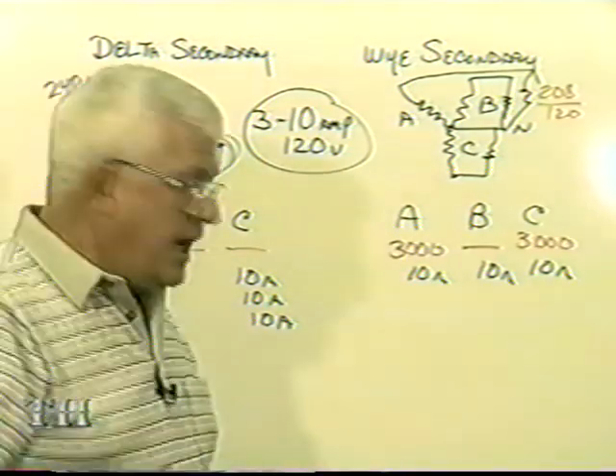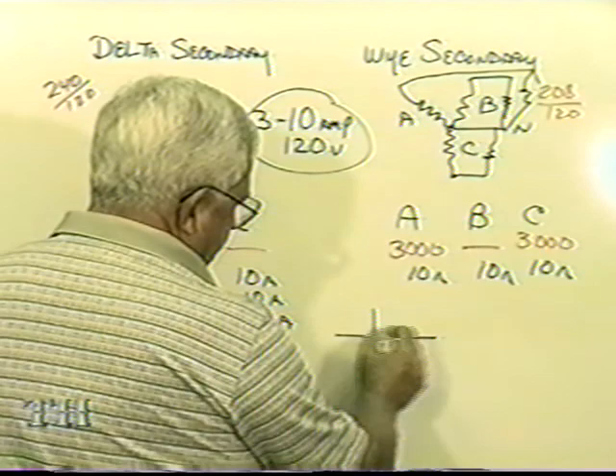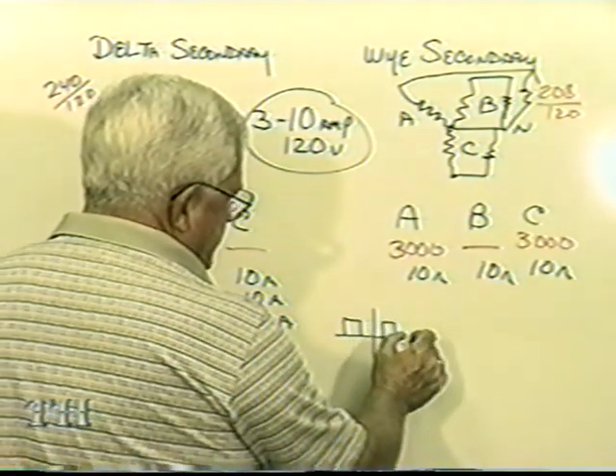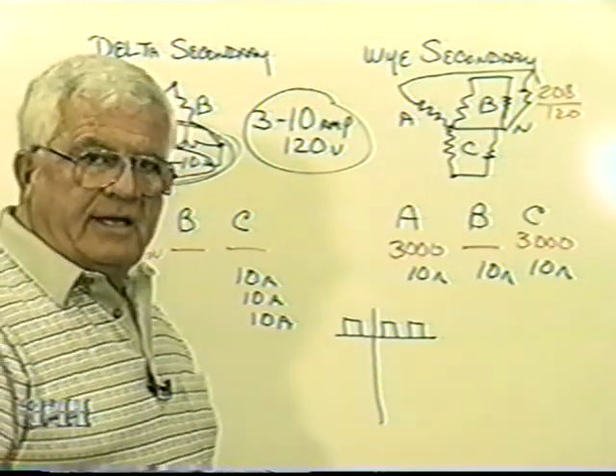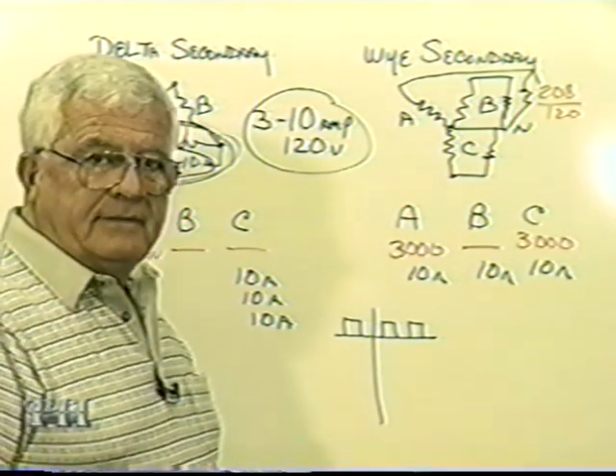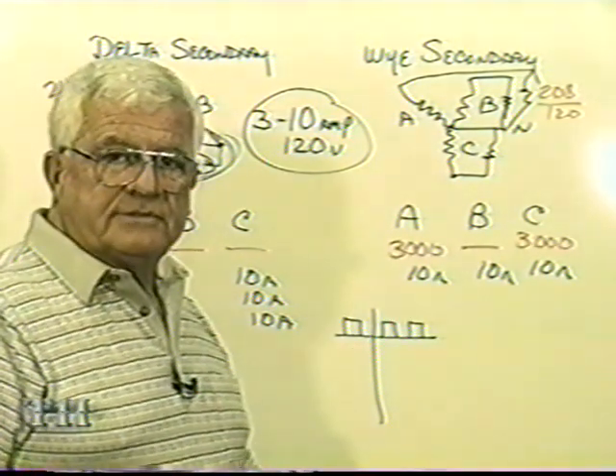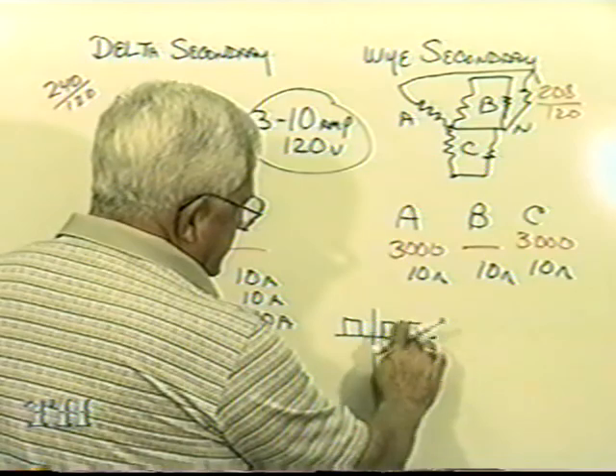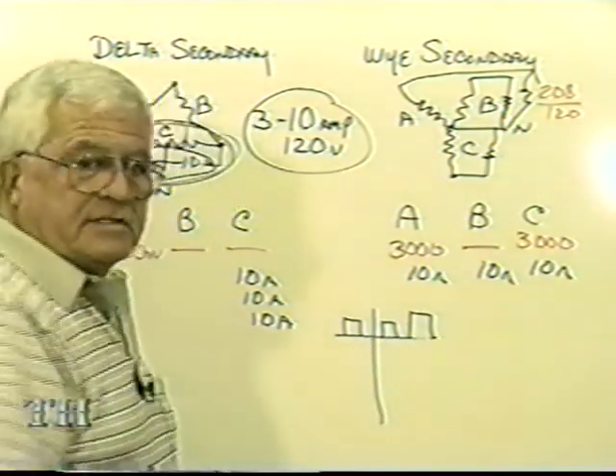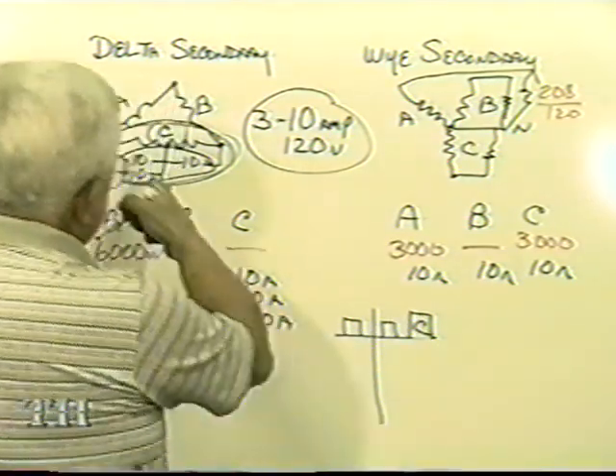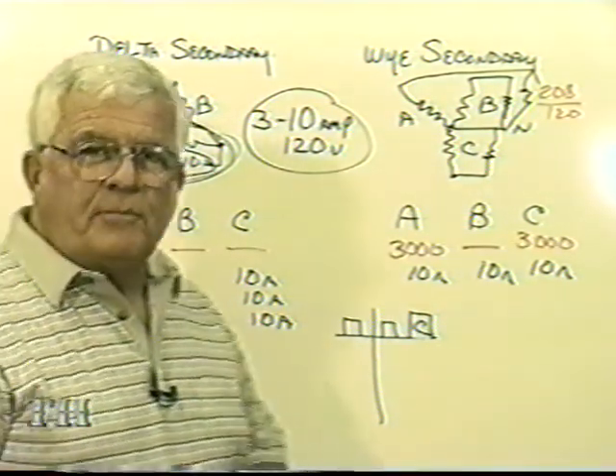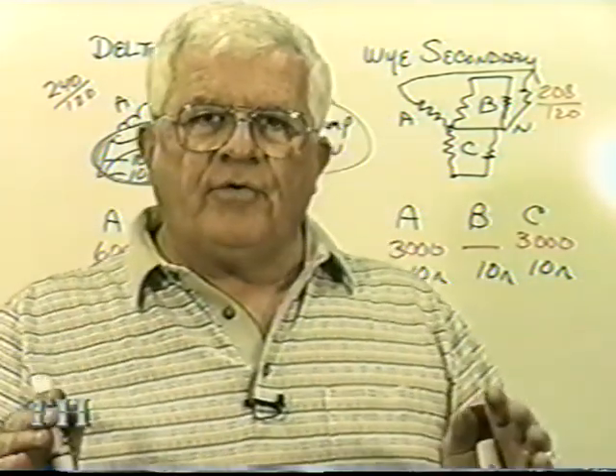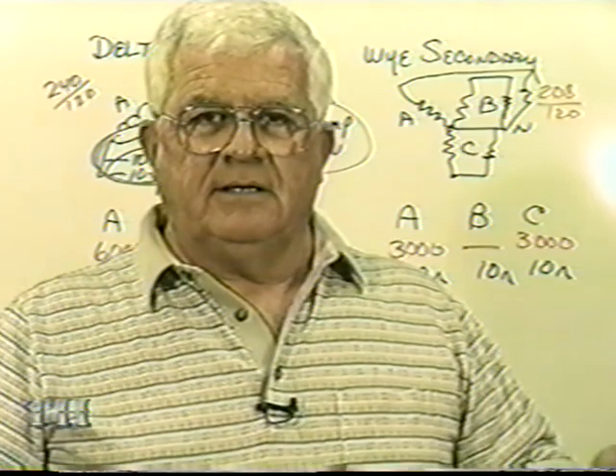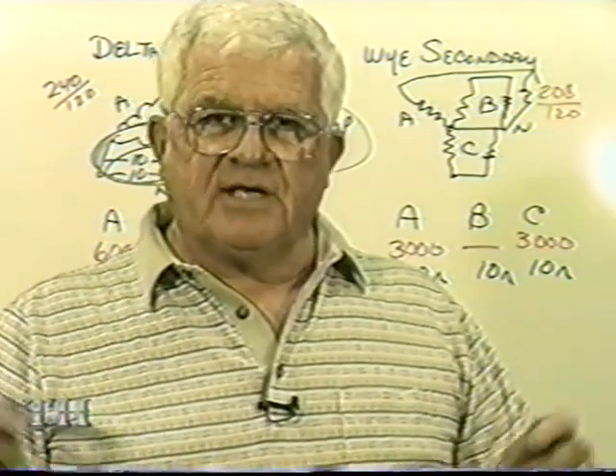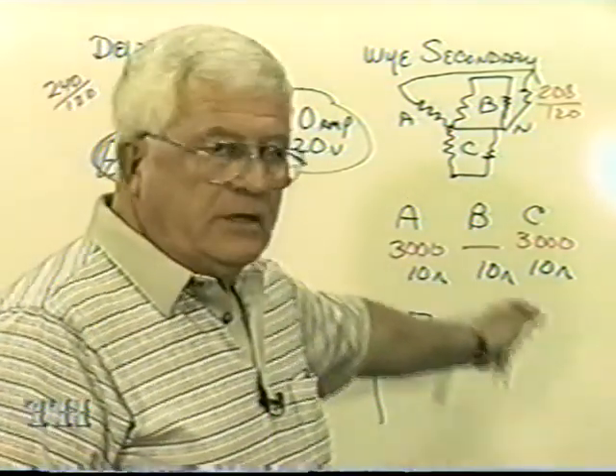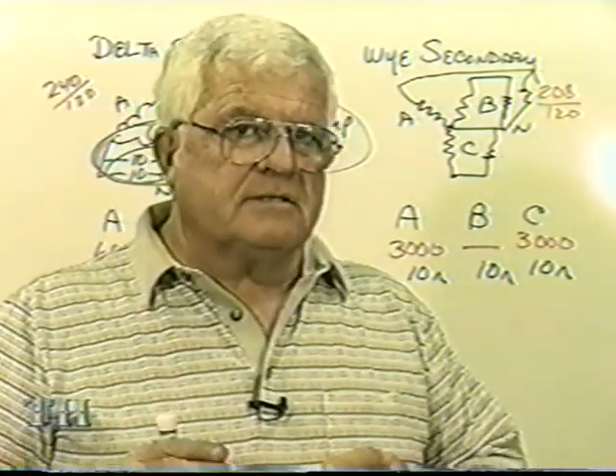When you drive down the highway and see a pole with 3-phase, 3 transformers the same size, that's Y connected, because I can balance my transformers. But when I see 2 the same size and 1 bigger, that bigger one is transformer C, delta connected. Transformer C has to carry a third of all the 3-phase loads, but it also has to carry all the lighting and receptacles, 120 volts. On a Y, your 120 volt loads can be balanced between each phase.